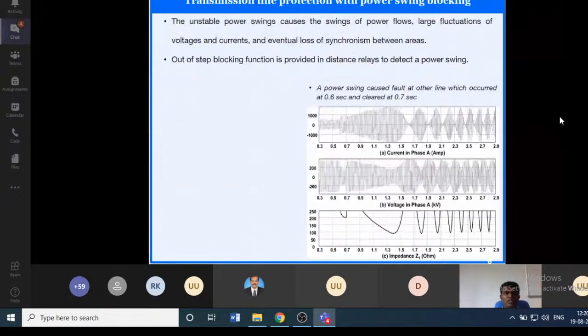Let us see one more challenge, that is power swing. What is the power swing? Power swing is when the system oscillates due to a fault occurring in some other line. For example, we have the relay for a particular bus, but due to the fault occurring in some other system line, the voltage angle is going to oscillate. The generator voltage is going to oscillate with respect to the reference bus, right? So that will give the oscillation between the two bus voltages and currents. See there, you can see the oscillation.